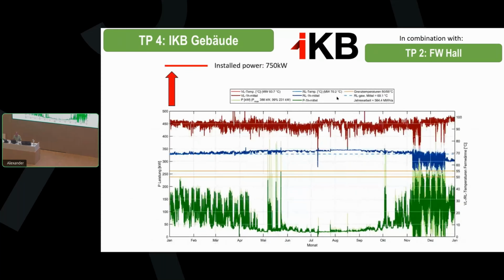What is the possibility? Just for example, here is what we found out in Hall. As you can see here, the blue line is the return temperature. The two orange lines are the goal, let's say; 50 to 55 degrees would be nice. And that's not seldom, that's not the only case. We are around 70 degrees here in the return temperature. So you see quite a big potential. The red line is the flow temperature, the inlet temperature on the primary side, something around 90 degrees.